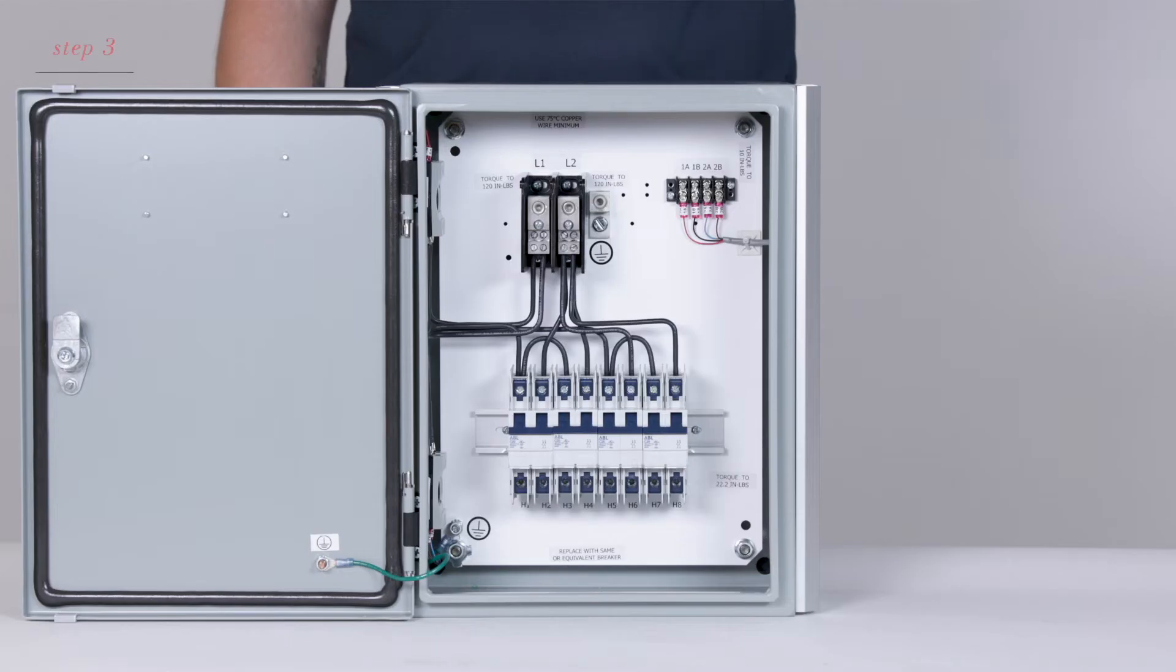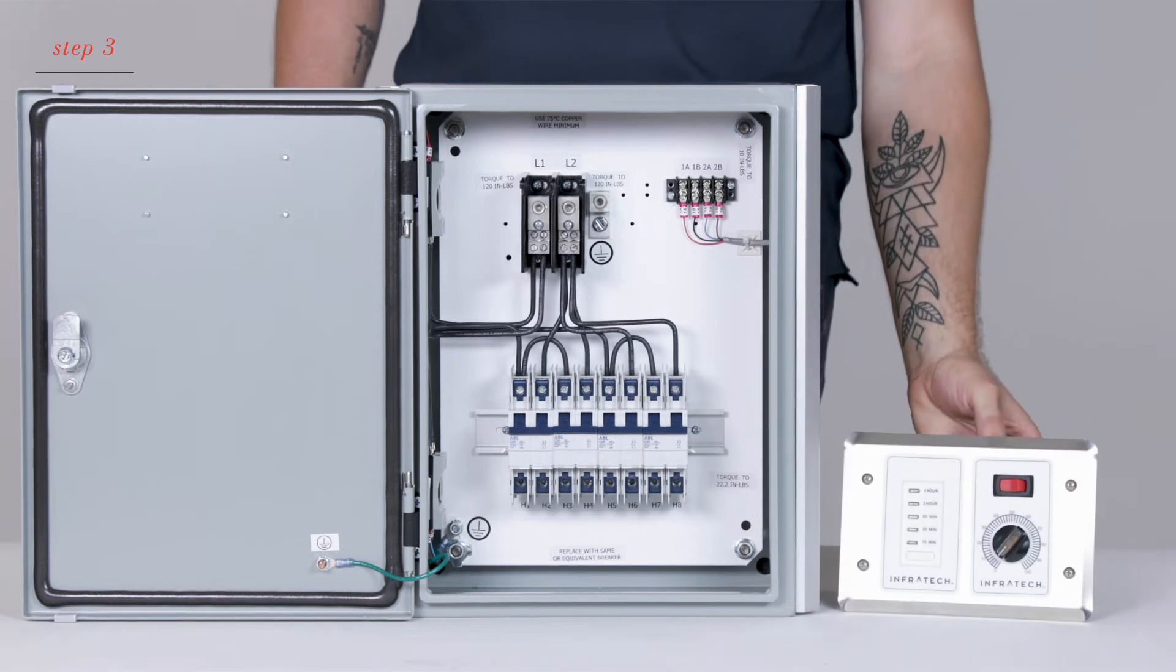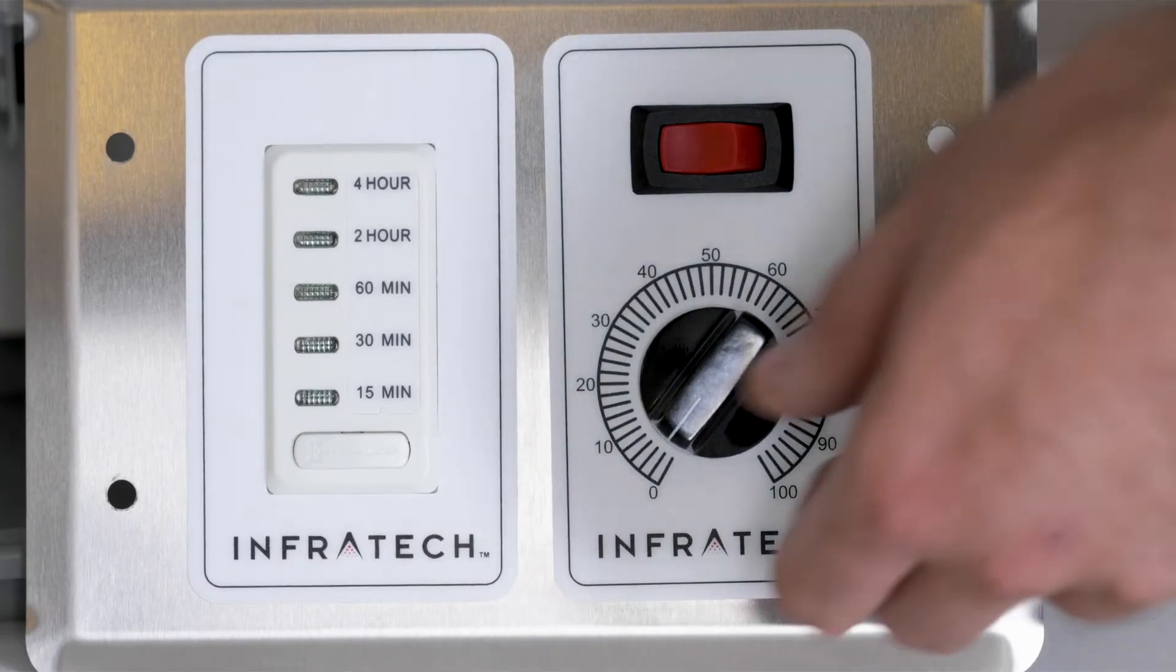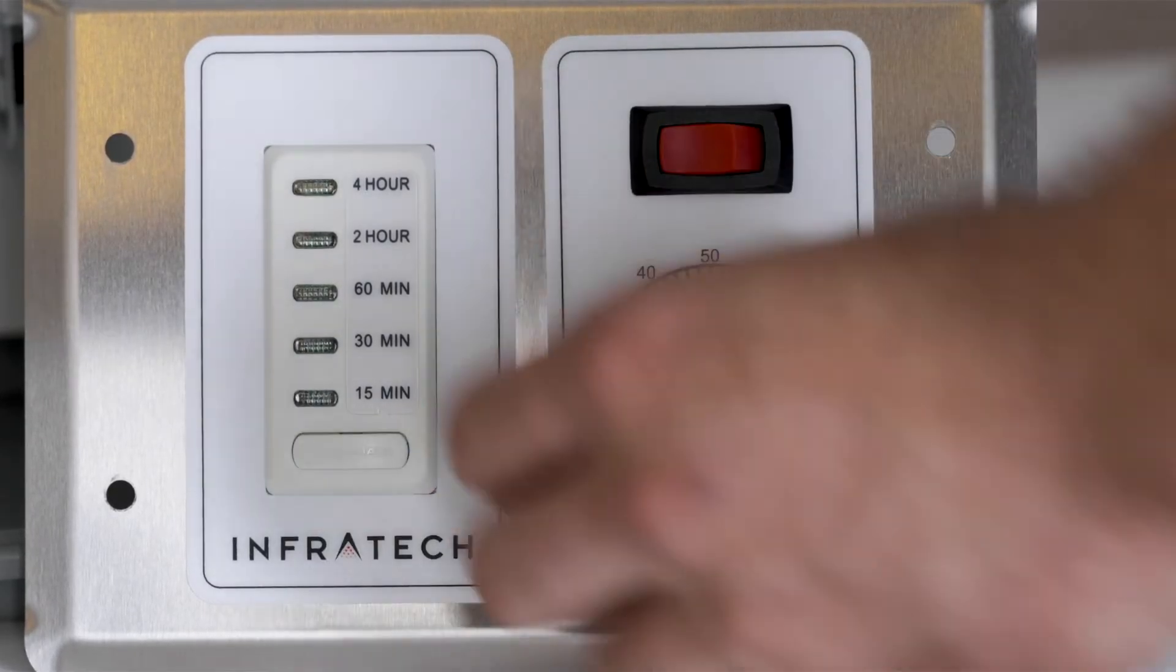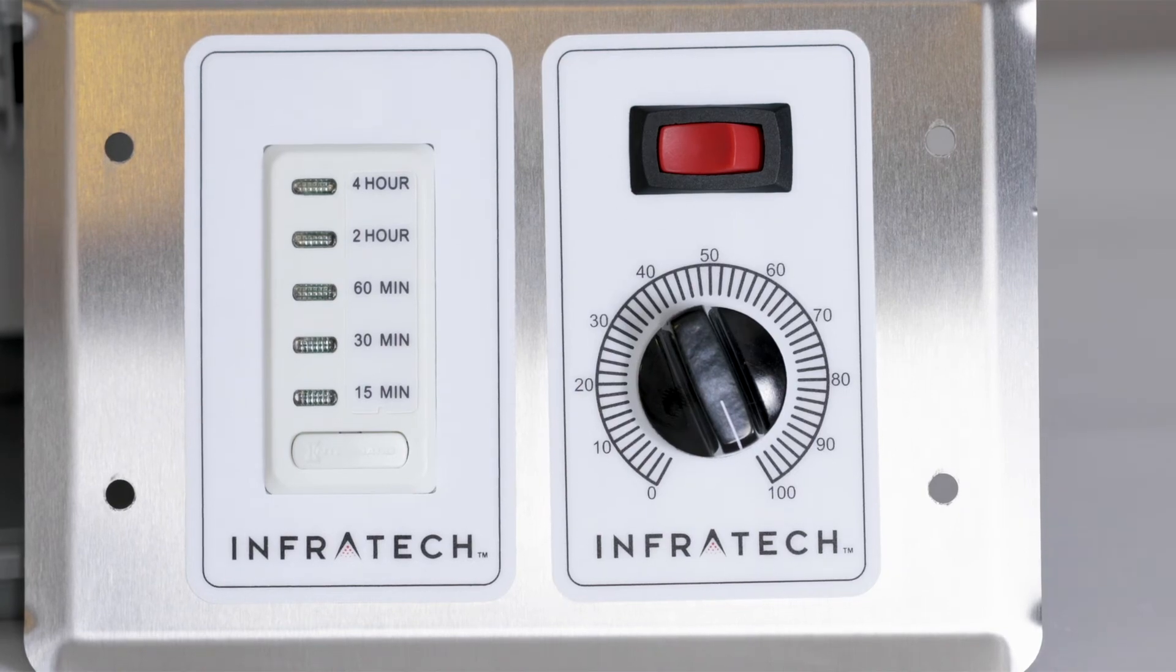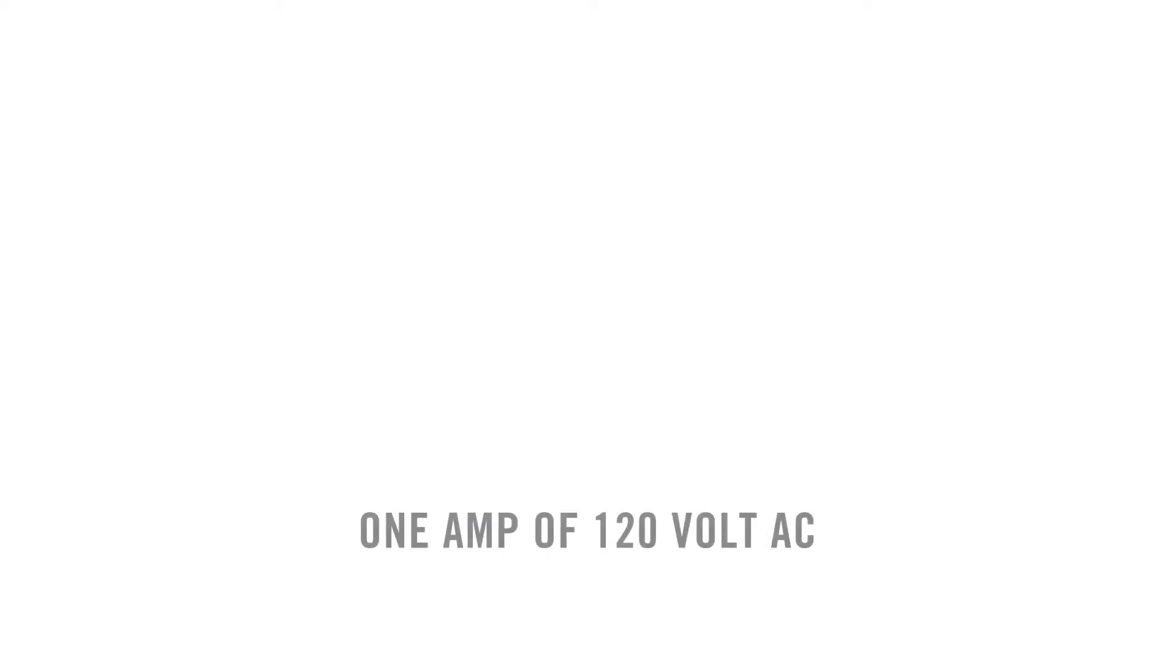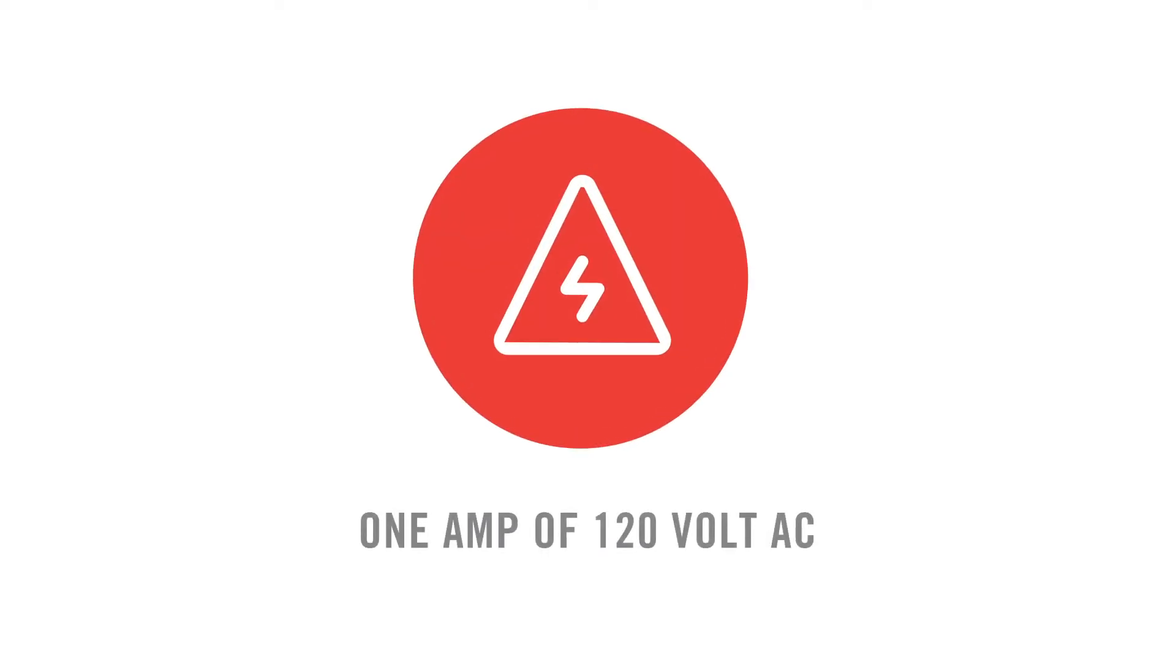Once the main feed is connected to the main distribution block, and the high voltage line is connected to the heaters, connect the zone analog controller with timer. The zone analog controller with timer will require 1 amp of 120 volt AC. This is typically taken from a local lighting or power circuit.